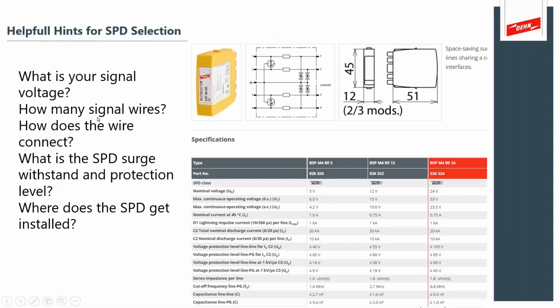Data circuits are much the same way. You have an operating voltage that you do not want to go above. If you know you have a 5-volt, very low voltage controlled sensor, then you want to stay with a very low voltage protection. If you have something that looks more like a 24-volt circuit, then you pick the higher protection operating voltage. How many signal wires? 2 pair, 4, 1 pair? What does the connection means? Is it stripped wires that you terminate into a patch panel for your phone room, or is it RJ45 connections? And then again, where does the SPD get installed? So on our data sheets, you'll see the things that are important for protecting your circuit, and diverting current away from your victim.